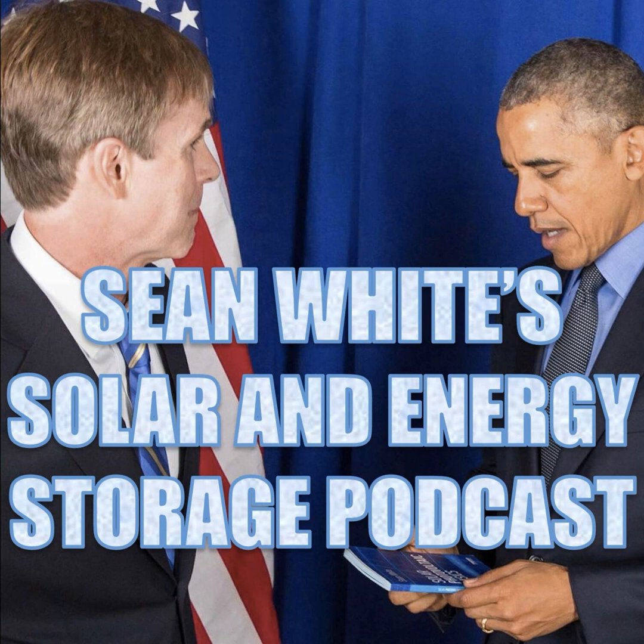So we have some batteries that are sealed that you can't add electrolyte to, like all our lithium batteries. You don't go adding electrolyte to a lithium battery. So let's just read the storage battery definition: a single or group of rechargeable cells connected together electrically in series, in parallel, or a combination of both, and comprised of lead acid, nickel cadmium, or other rechargeable electrochemical types. Terminal is what you connect to. That's the terminal post of a battery. But just throughout the electrical code, when it talks about terminals, that's where you make the connections.